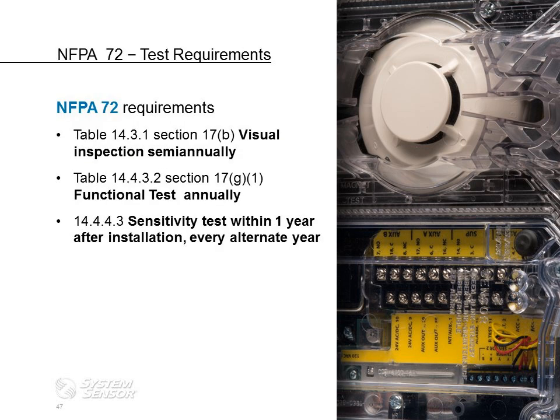NFPA 72's test requirements are laid out here for you. The requirements from 72, in Table 14.3.1, Section 17B, require that we perform a visual inspection semi-annually. So every 6 months, per the standard, to be code compliant, we're required to do a visual inspection of the duct detector. That visual inspection basically includes making sure it's mounted correctly, that there are no leaks, that it's sealed, that the LEDs are flashing, and that it's in a normal state. The second test that's required is a functional test. Duct detectors are required by code to be functionally tested once a year. And the third test that's required is the sensitivity test. Sensitivity test is required within 1 year of commissioning or after installation, and then every alternate year after that out to 5 years.